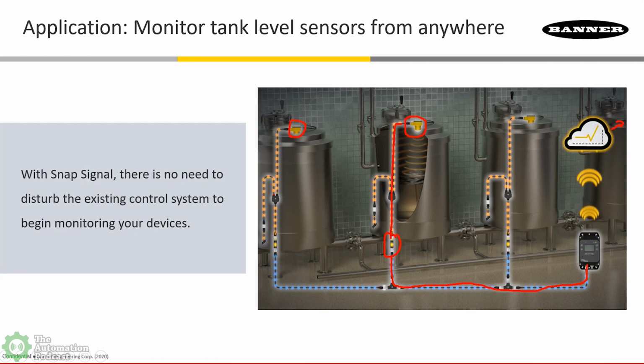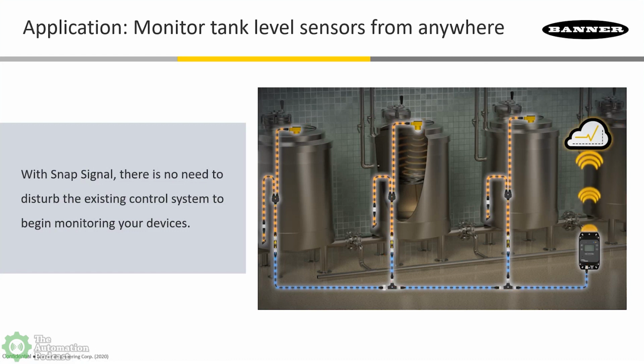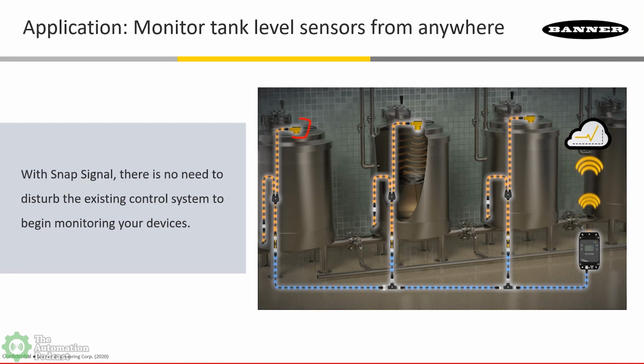What's powerful here is that if you have sensors already installed talking to your existing control system, you could harvest that sensor data without disturbing those controls by using something as simple as an M12 parallel wired splitter to still send the sensor signal back to your PLC—one branch going back to the PLC, and one branch going into the converter.